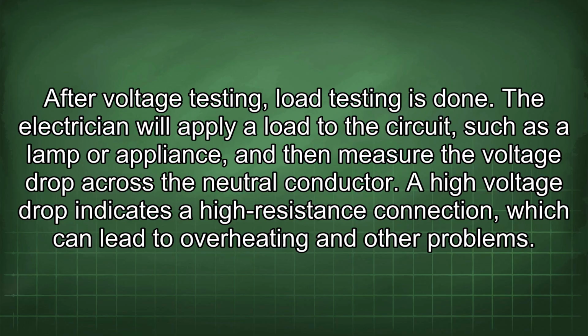After voltage testing, load testing is done. The electrician will apply a load to the circuit, such as a lamp or appliance, and then measure the voltage drop across the neutral conductor. High voltage drop indicates a high resistance connection, which can lead to overheating and other problems.